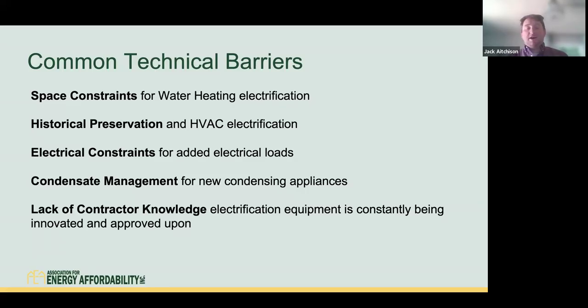Electrical constraints for added electrical loads - when you're electrifying a building, you're adding electrical load, so do you have the capacity to support those loads? And then condensate management for new condensing appliances. Heat pumps create condensate, and that condensate has to be drained to a drain somewhere in the unit, and that can be challenging. So I have a case study around that as well.